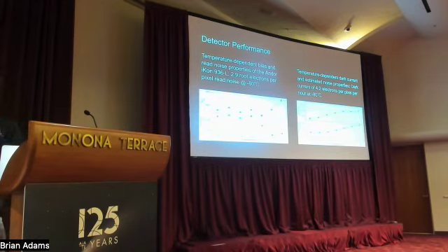We have a couple of options to read it out. This is the low speed, or whatever we call it. And then it has a dark current of 4.2 electrons per pixel per hour at -80 Celsius. So Will did this great analysis here that basically told us you have to operate at -80 Celsius if you can, for the lowest dark current. That's why we choose to operate at -80, which is about as cold as it can get. And so we get the best performance there.